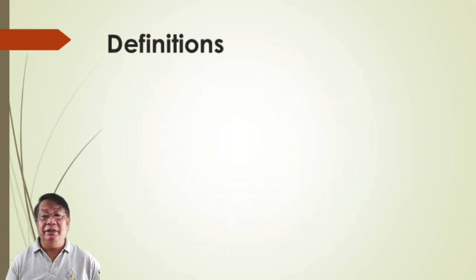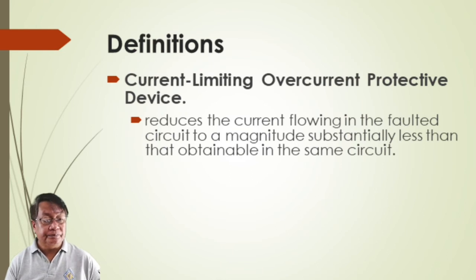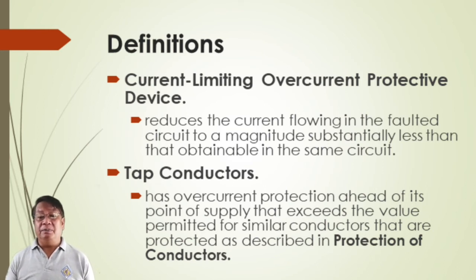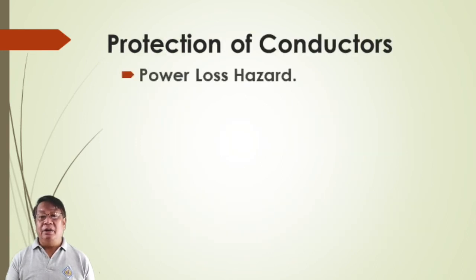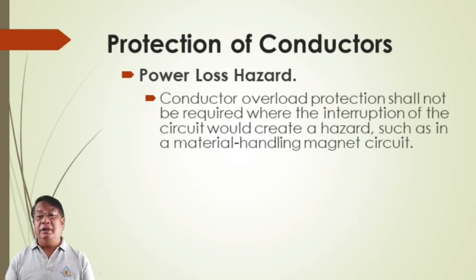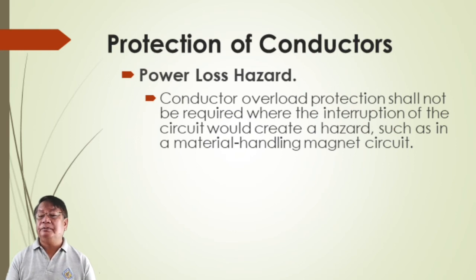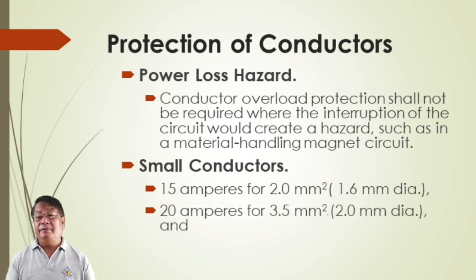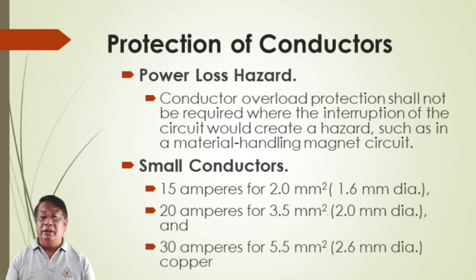A current-limiting overcurrent protective device reduces the current flowing in the faulted circuit to a magnitude substantially less than obtainable in the same circuit. Conductor overload protection shall not be required where interruption of the circuit would create a hazard, such as in material handling magnetic circuits. For small conductors: 15 amperes for 2.0 mm², 20 amperes for 3.5 mm², and 30 amperes for 5.5 mm² — this is for copper.